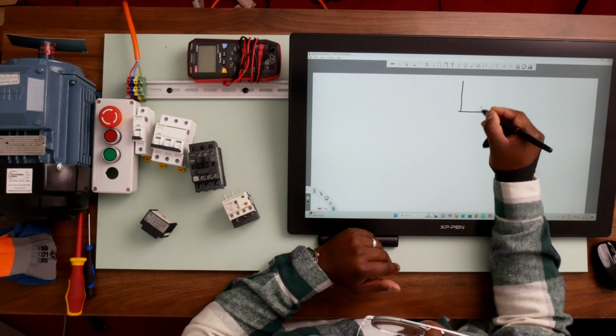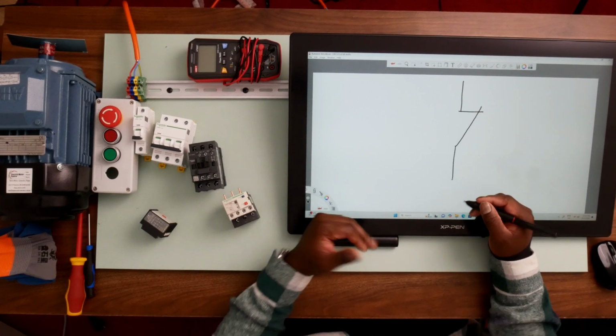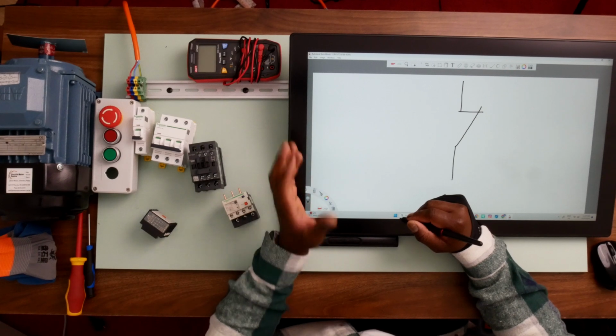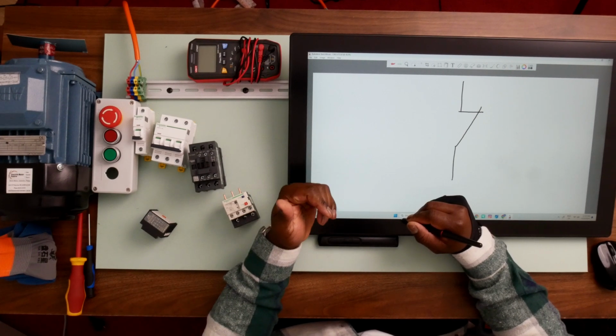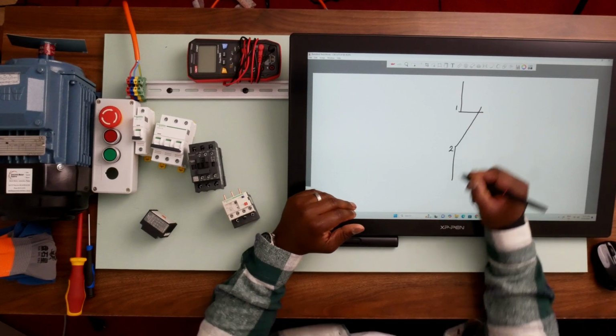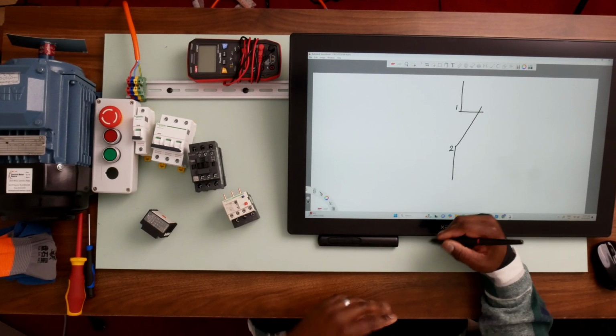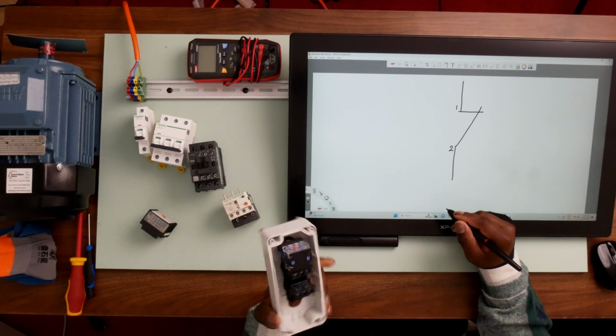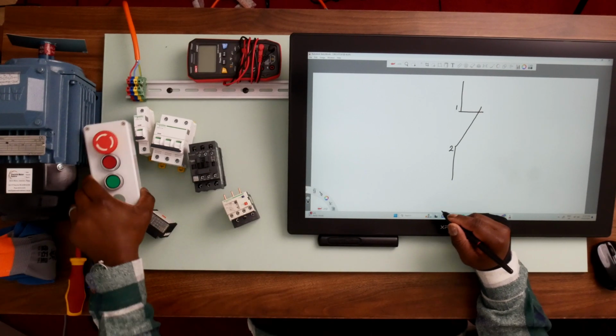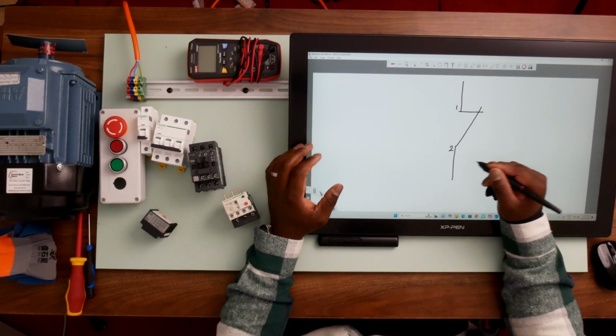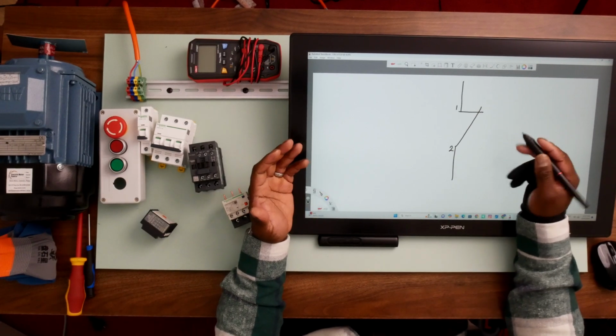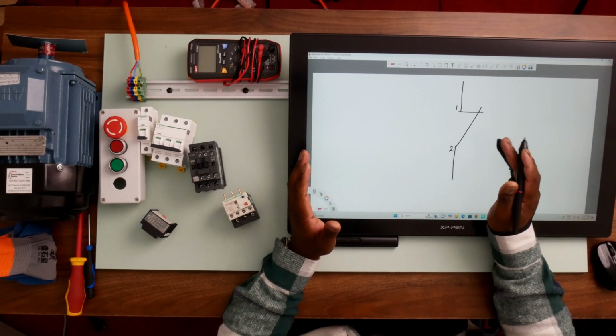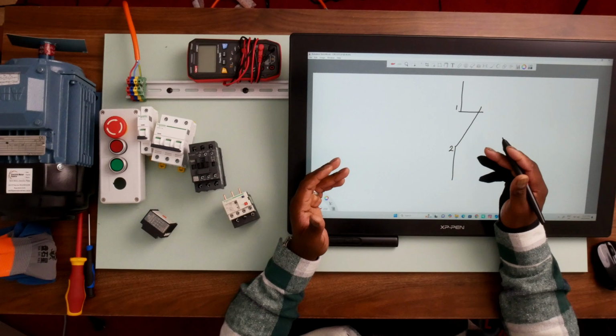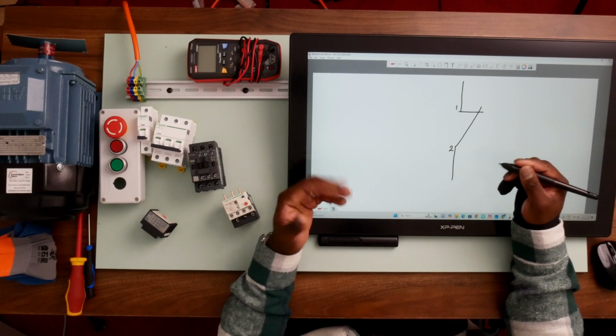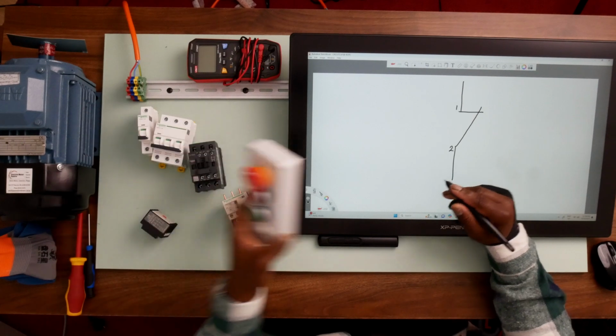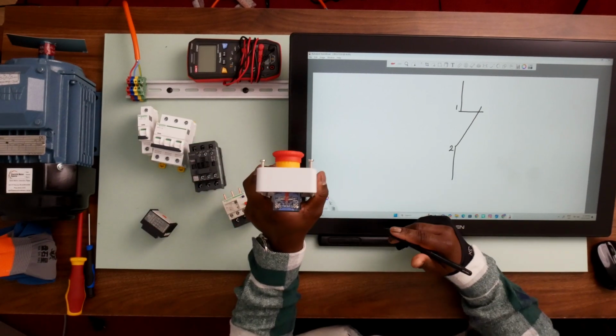So the basic contact on an emergency stop button is a normally closed contact, but now we're going to require something that is going to tell us that it's an emergency stop button. So the first thing we do is to label our contacts here 1 and 2, but that all depends. The one that I have here is labeled 11 and 12, but most emergency stop buttons have contacts labeled 1 and 2, but we know that any number that ends in 1 and 2 is a normally closed contact, and it's perfectly fine for our needs. So the common emergency stop button is what we call a mushroom head, like this one, because it looks like a mushroom head.